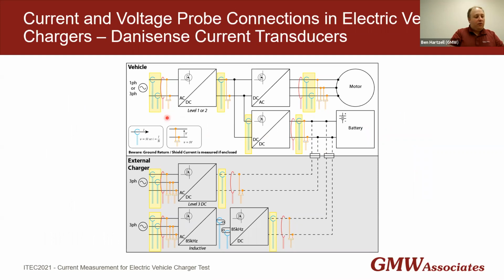And the reason you might want high accuracy measurements is particularly for power efficiency measurements. So if you look here again in our diagram, I've highlighted the AC and DC points, but I've also added voltage connection points, which we're not covering voltage measurements here today. But for good quality power measurements, you need both a good quality current measurement as well as voltage to calculate total power. And you need good current phase response in addition, not just amplitude response. You need both amplitude and phase for good quality power efficiency measurements.